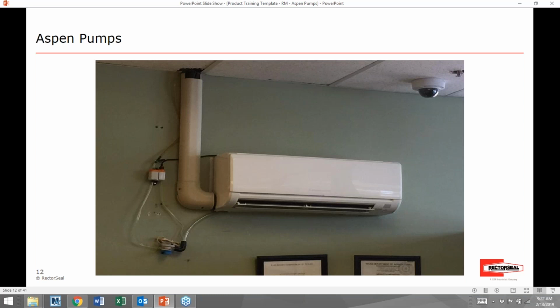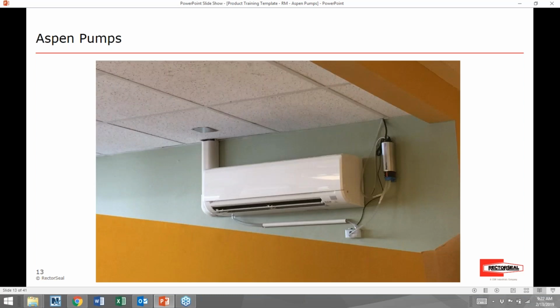The big takeaway here is that this picture and the next one are both Mitsubishi machines. And the average consumer just looking at that for the first time would never accept that if it was being proposed to place in their home, because that's the picture they have. They're also tying the quality of that install back to Mitsubishi, so it detracts from the good name of Mitsubishi. So across the way we have this guy here, a completely inappropriate installation, but this is real life, guys. The other thing to note here is that Blue Diamond pump. This is one of the pumps that's supported by Mitsubishi. And as you can see, for a residential or light commercial application, that pump is never going to work in this application. You'll never fit it inside the back of the unit. It's going to have to go in a remote location. We'll talk about that in a little more detail as we get to the product applications.